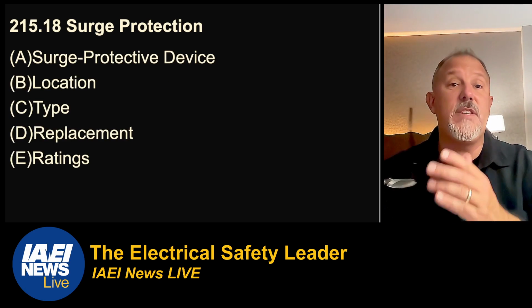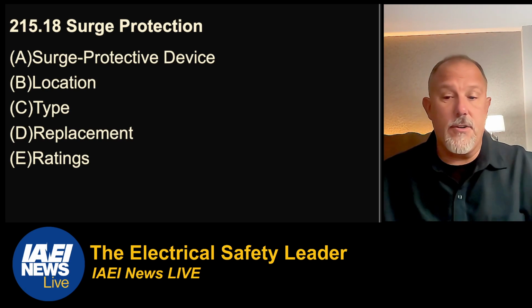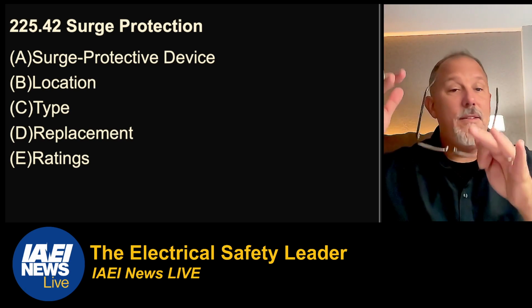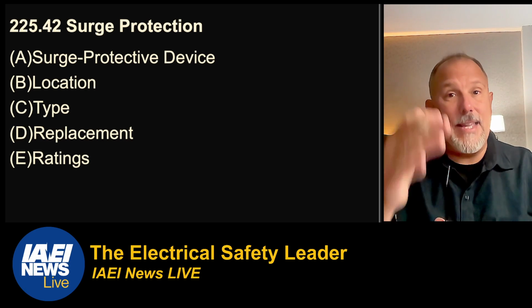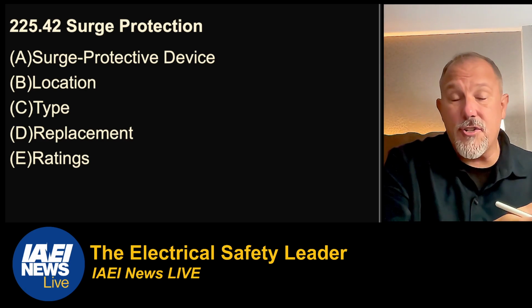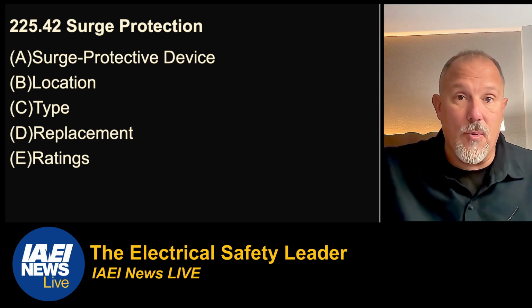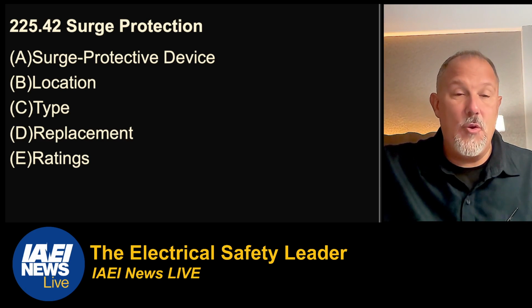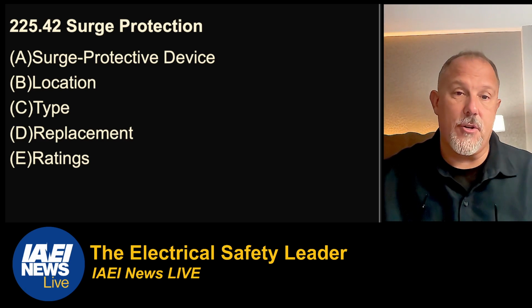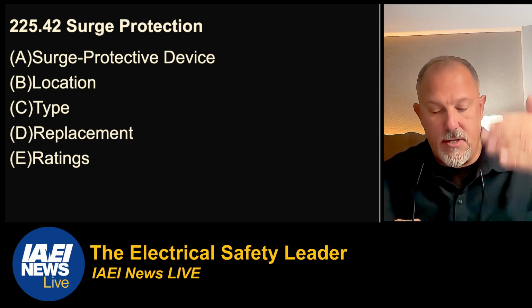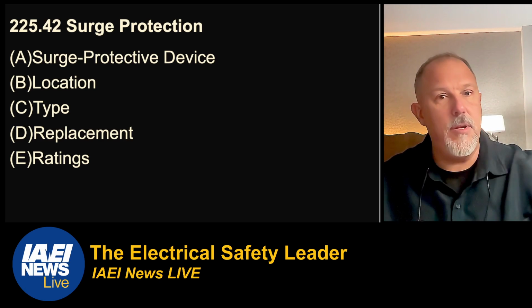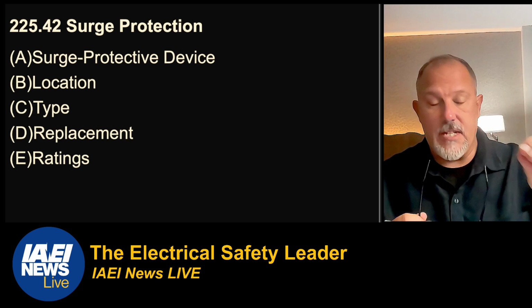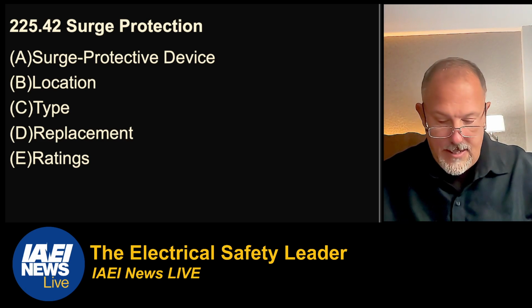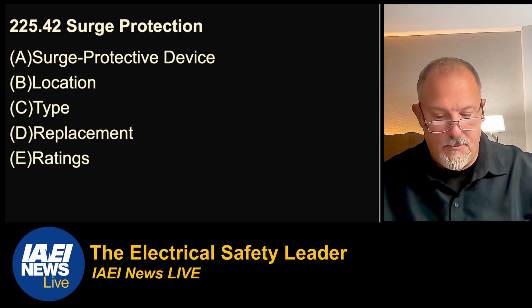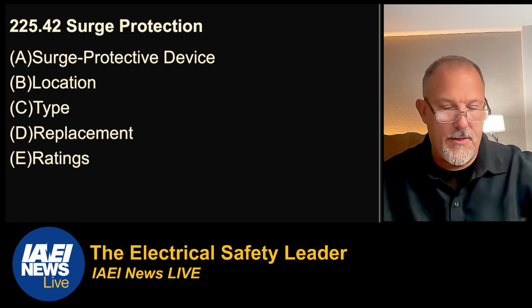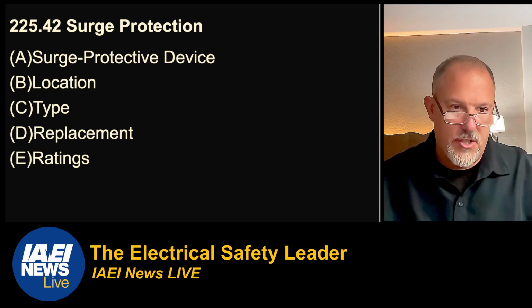Now, there's a few other areas. 215, very similar requirements for feeders, and then also in 225, the same type of language. Because again, they want the surge protection close to the structure. You don't want that surge product out there at the road at your service equipment. You want it at the end of that feeder feeding a structure. It's the same locations, dwelling units, dormitory units, so all of that language is the same in A or B. In B, the location is the same, the type 1 or 2, the replacements are there, and then the rating, same 10K. So those are just two other areas to be mindful of.